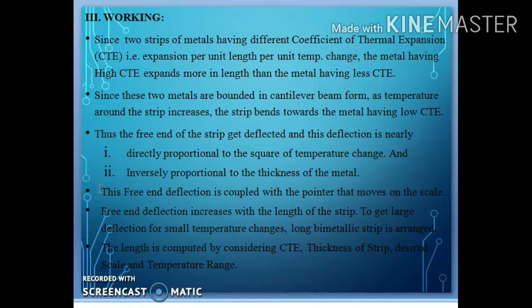The free end deflection increases with the increase in length of the strip. To get a large deflection for small temperature changes, a long bimetallic strip is arranged. The length is computed by considering the coefficient of thermal expansion used in manufacturing the bimetallic strip. Also, the thickness of the bimetallic strip is considered, and the desired temperature scale and desired temperature range also have to be considered while designing the length of the bimetallic element.